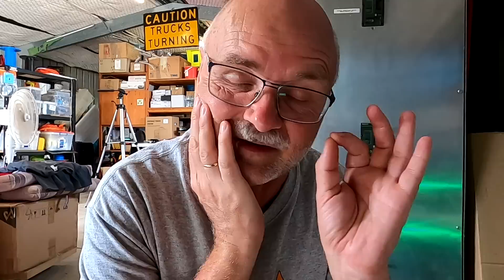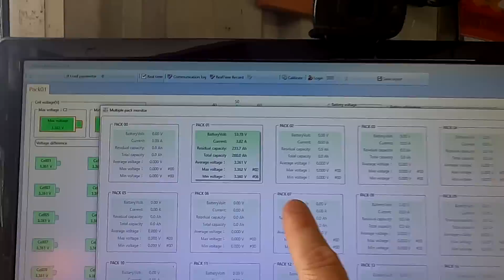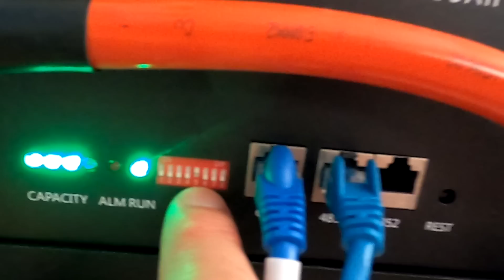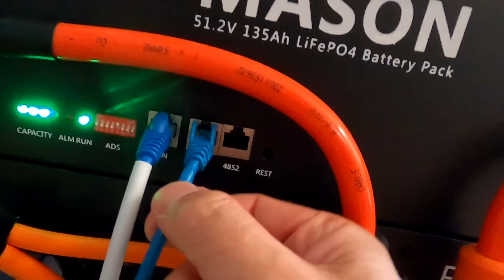None of the first four switches is set, so this must be battery pack 0 - that's exactly what we found out: if none of these dip switches are set, it's pack 0, not pack 1. So in theory pack 0 should be available, but it's not communicating. Why not? Because dip switch 5 is set and turns on CAN communication, which then turns off RS485 communication to any external device. It still keeps internal RS485 communication to the next battery pack, but not to our computer.